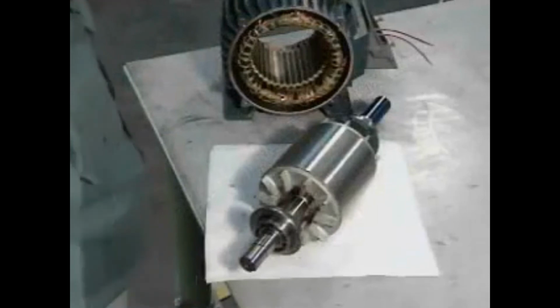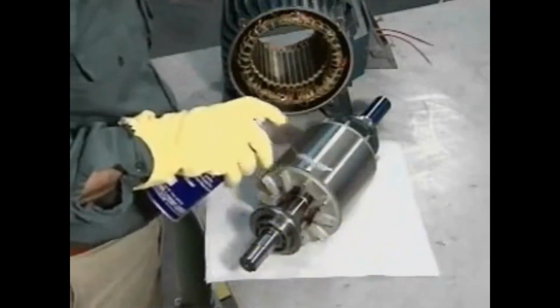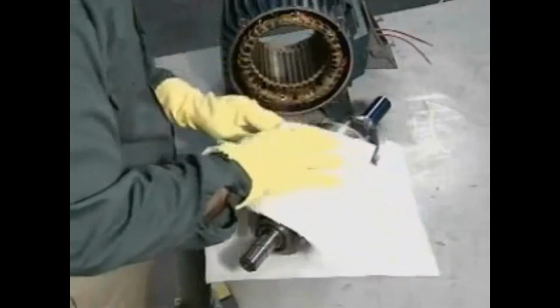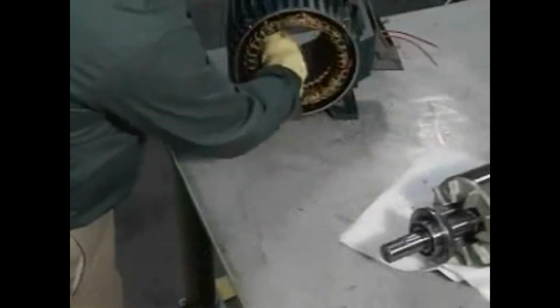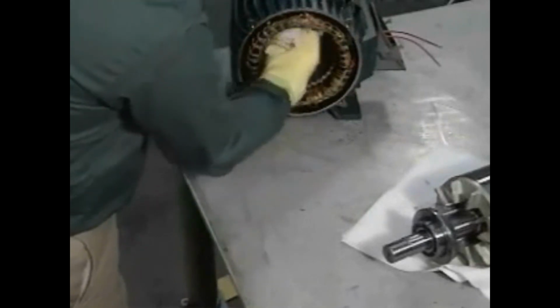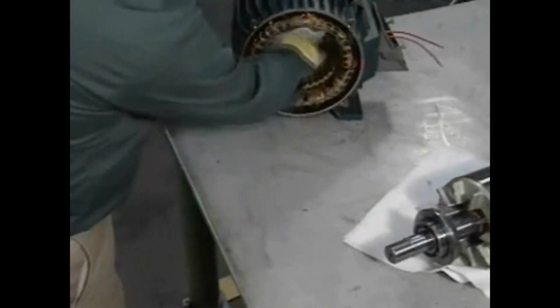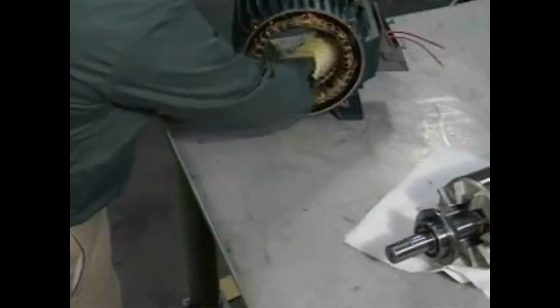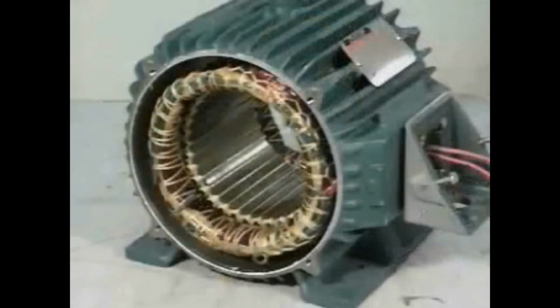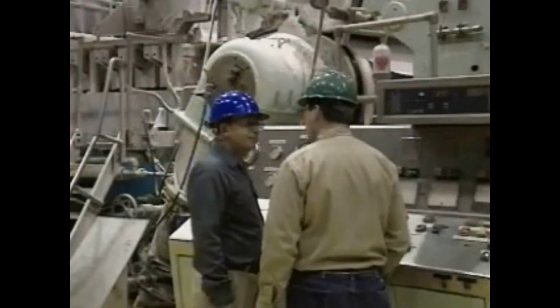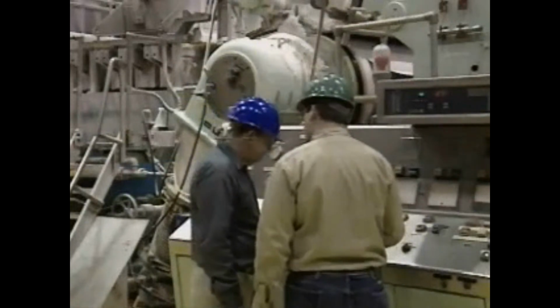Once you have inspected the rotor, clean the rotor and stator with a soft lint-free cloth and approved solvents to remove dirt buildup that may hide problems. Take care to prevent damage to the windings and to prevent loose dirt from being rubbed into the winding, as this can reduce insulation resistance. After cleaning the stator, inspect the windings for discoloration and signs of abrasion. Inspect the pole pieces for scraping, rubbing, or overheating. If you detect any problems during the cleaning and inspection process, inform your supervisor.